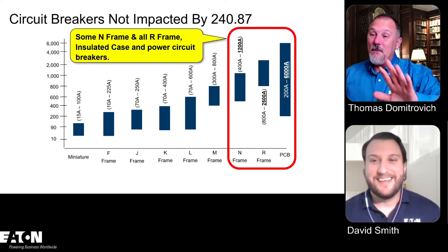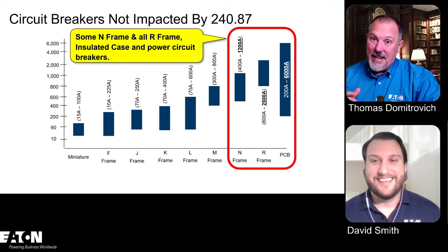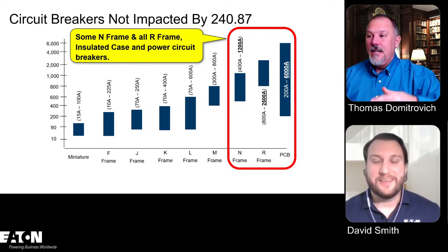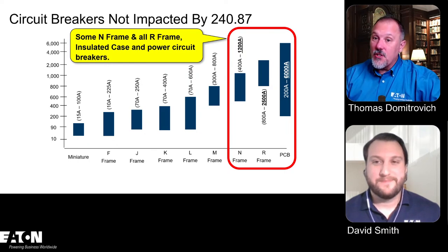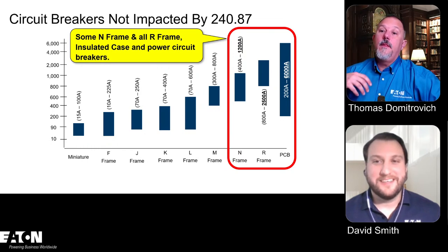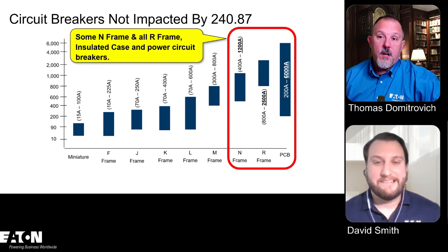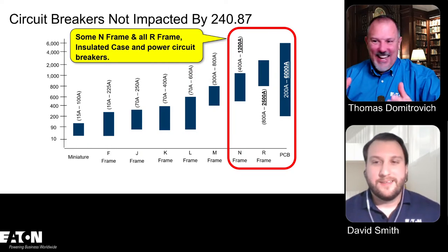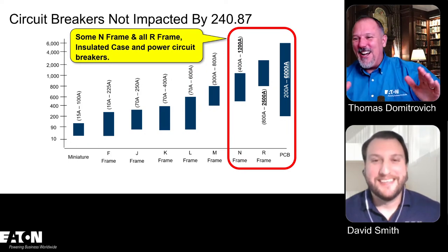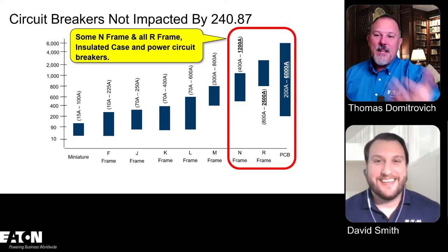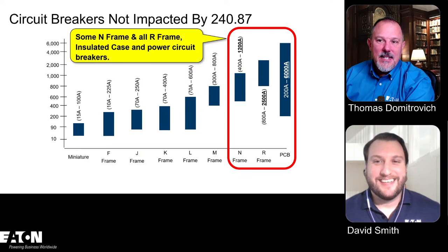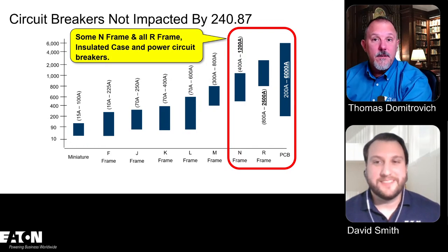Now, okay. So the panel agreed they want to go to 800, but here's the catch. Because not all manufacturers have the solutions like we have, all the way down. Right. They felt more comfortable going to 1,000 amps. Okay, which I know, I saw the light bulb go off in your head, because it doesn't make sense. I have a 1,200 amp breaker. If I'm on 1,000 amps, I adjust it down. So that 1,000 amps really is already covered. What's the difference? Right. Yeah.